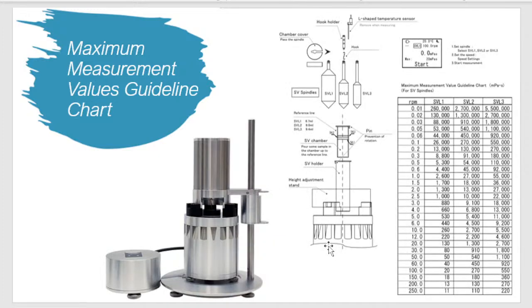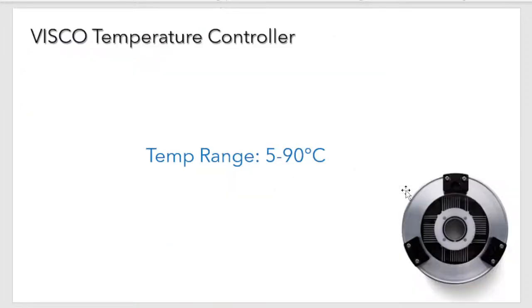For the VISCO BL benchtop viscometer, you would use a similar table. It also has three spindles — SVL1, SVL2, and SVL3 — and different RPMs. Similarly, if you're looking at 10,000 cP, you would likely choose the SVL2 spindle at 2.5 RPM.